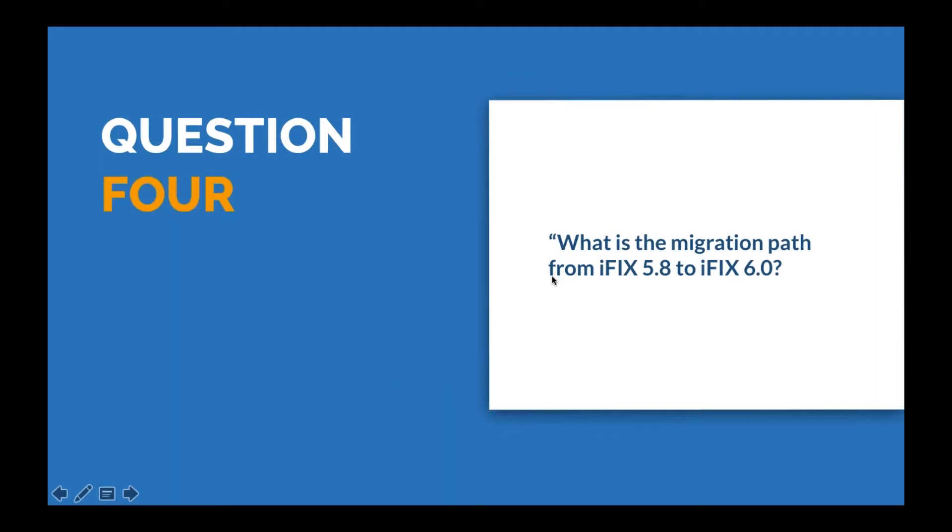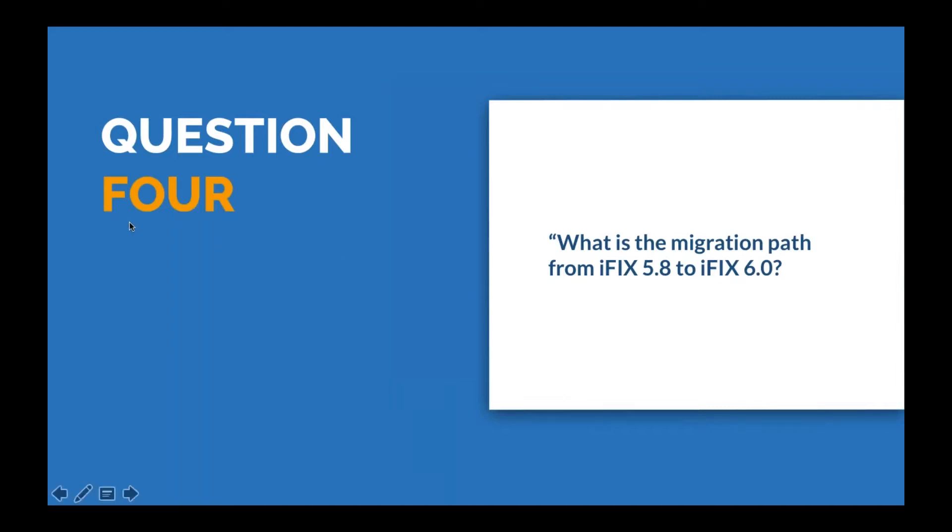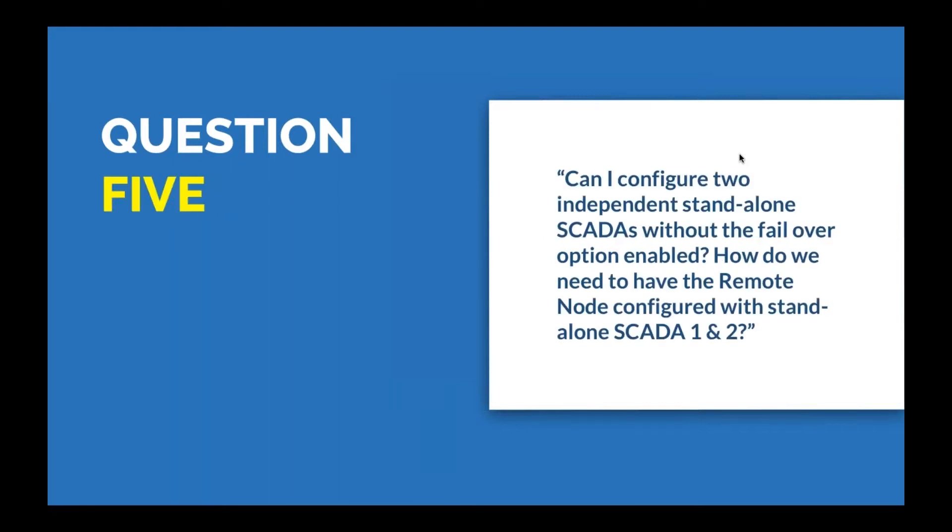Scott adds that they tested upgrading from 5.9 to 6.0 many times. The upgrade should be fairly straightforward. Always follow normal operating procedures when doing any kind of upgrade. With 6.0, because of the long tag names, you do have to upgrade your clients first because older clients will not connect or communicate with the iFIX 6.0 SCADA node. A follow-up question asks if program blocks are still supported in 6.0.